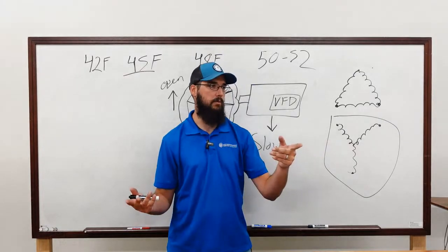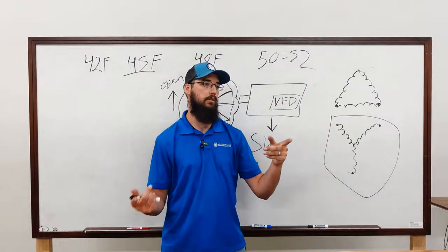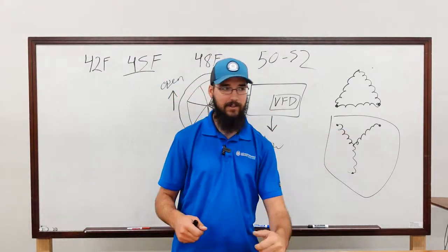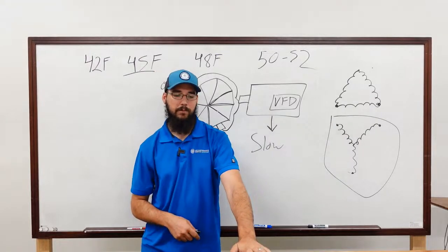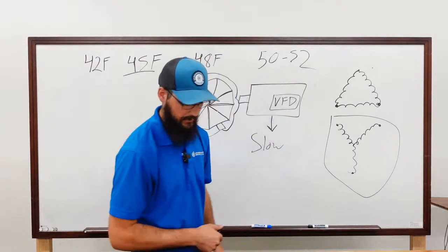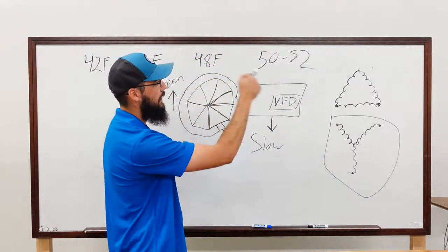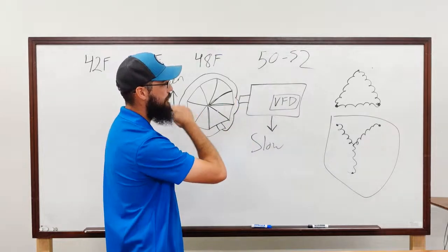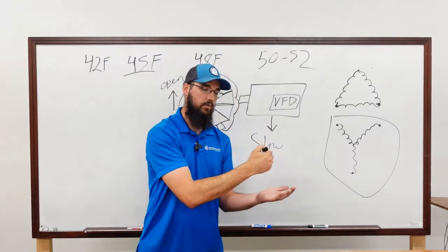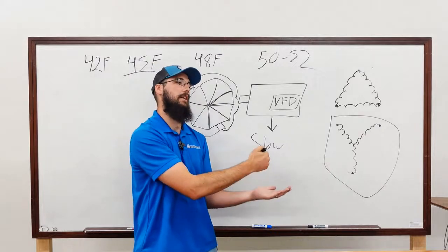So you may be right. I think 208 we wire Y, 460 we roll delta. That's right. See? All the numbers line up in delta. That's why you hire good people, guys. They can remember stuff you sometimes forget. I'm paying good money. So, anyway, yes, the vast majority of our motors, we run 460, and so they run a delta configuration.